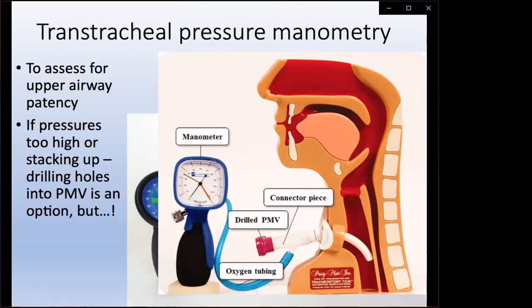Also, knowing that the Passy-Muir Valve especially is a one-way valve, a no-leak design valve. Once you drill a hole into it, it's no longer a one-way valve, because they can breathe out via the hole as well. It's no longer a closed valve, because there's a hole that can leak all the time. So it really defeats the purpose of a one-way valve. So it may be an option, but definitely caution needs to be taken.